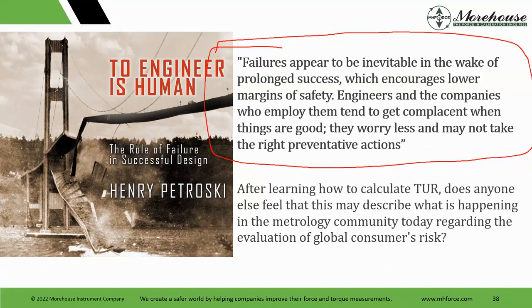The same thing happens with measurements. I talked to a person who was doing scales, and they were doing all the scales at their location and then shipping them to other places for use. And I said, well, the gravity's different at other places. How do you account for it? And he was just stymied. He said, if I'm inferring correctly, you're telling me that I've been doing this wrong for 20 years, and I refuse to believe that. And I said, well, yes, I am telling you that, and yes, you have been doing it wrong for 20 years. So that's tough.